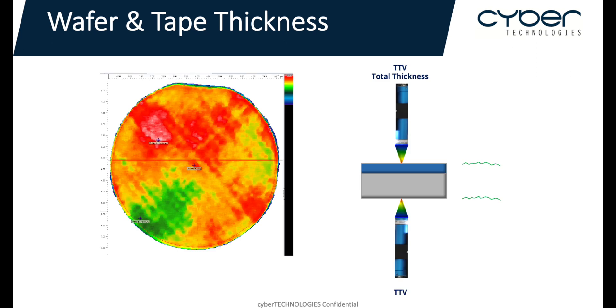However, due to the refractive properties of the tape layer, measuring just the wafer itself can be a challenge. The system uses dual-sided sensors, one that measures from the top and one from the bottom. As the top sensor measures through the tape layer to the top surface of the wafer, the light gets refracted by the tape, thus affecting the light that bounces back to the sensor, causing the wafer thickness measured to be much higher than it actually is.